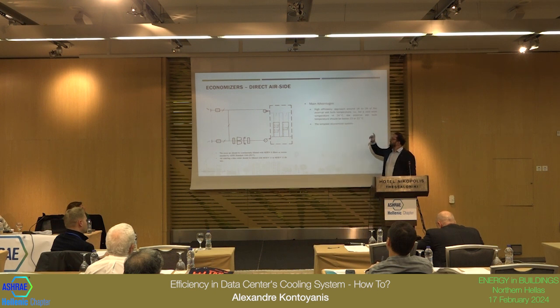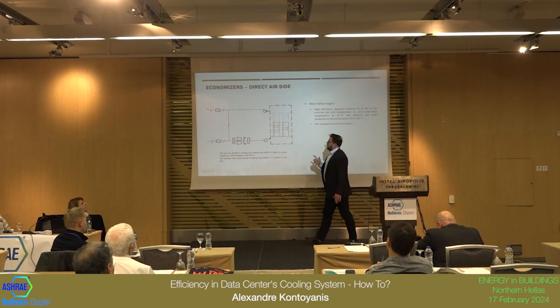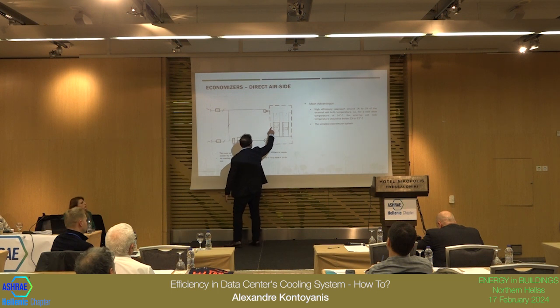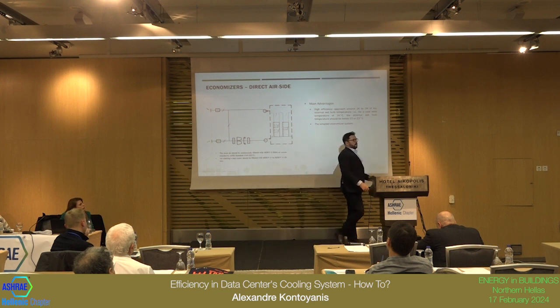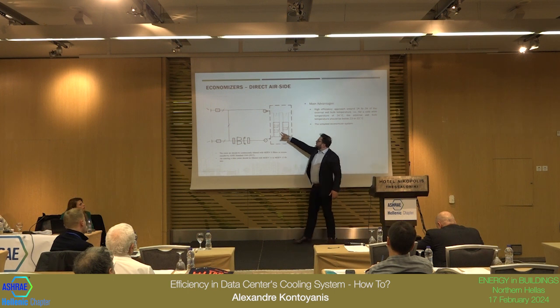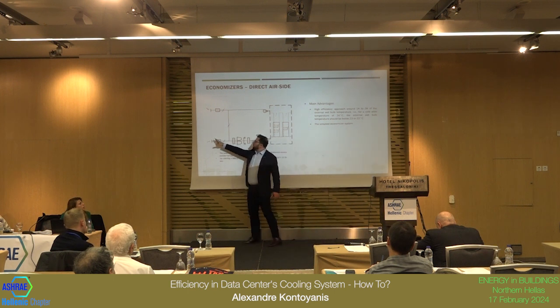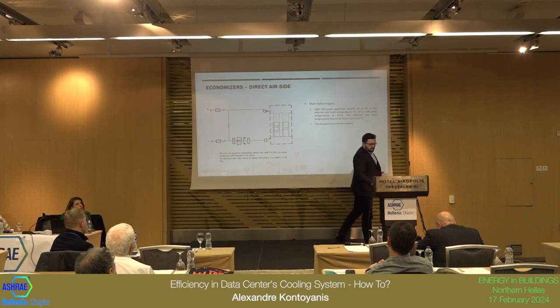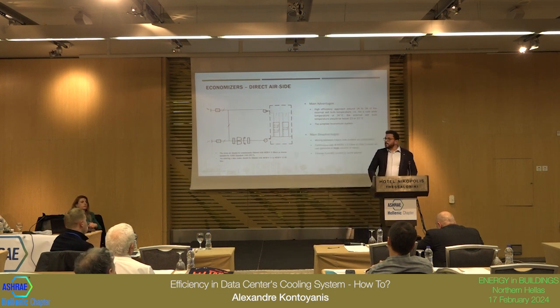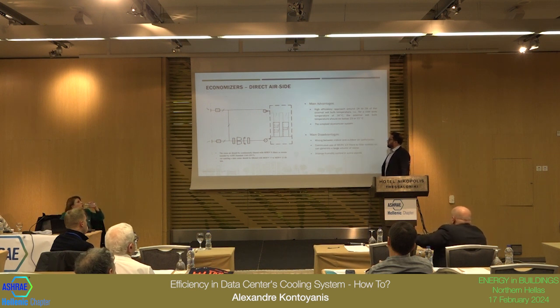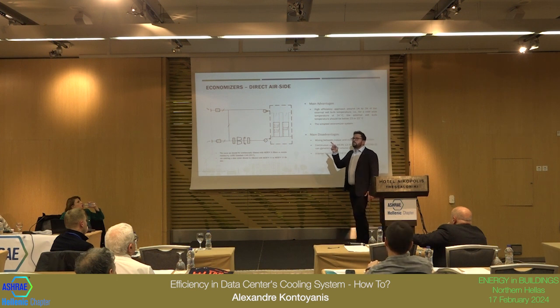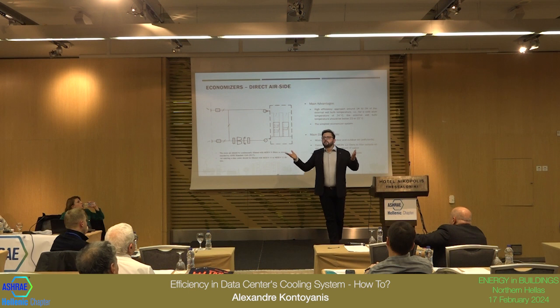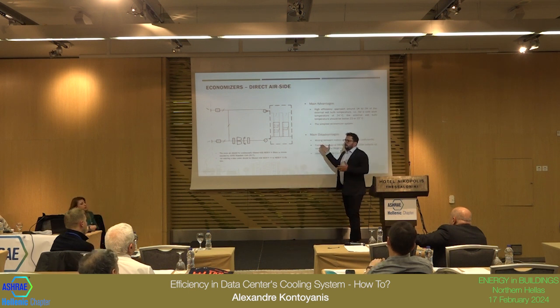Advantages: high efficiency. We have the approach. The approach is the difference between the temperature that we are looking for, the standard, and the outside temperature. The difference between those two is 1 to 2 K. It means if you want 20 degrees Celsius here, the outside should be below, 18 or 19, for example. So it's very efficient, and it's simple, but you have some problems. You mix the outside air and the inside air, and you don't have control of the quality of the outside air. It can be polluted. For example, if some trees start to burn around, there will be smoke in the data center. It's a problem.